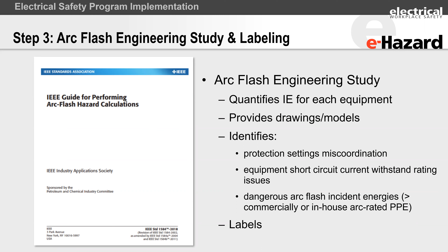And then when we talk about the labels, the minimum requirements for labels are: you need to stipulate the voltage, you need to stipulate either the incident energy or mention to the worker what type of clothing they require, and the third mandatory requirement is the arc flash protection boundary. However, for these labels to be useful, we suggest that you provide a little more information. That means come up with some sort of a system where you discuss levels of PPE, talk about what is the equipment name, where is it fed from, what was the date that the label was applied. And folks, all of these can be customized. The label can be something that you can specify, but don't specify this in isolation. Talk to industry experts, talk to consultants, talk to folks who have rolled out these programs and ask them, hey, what worked, what didn't work, right?